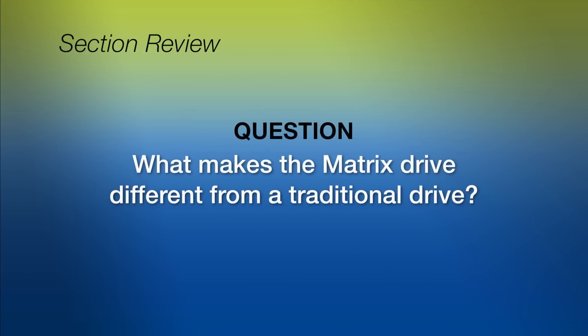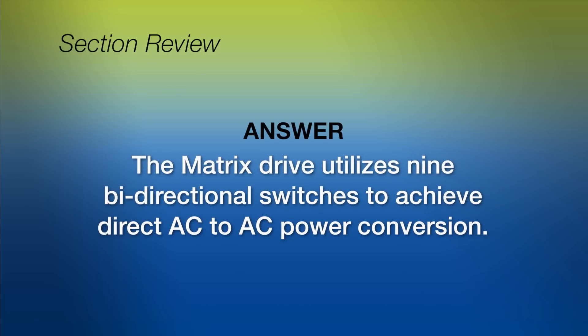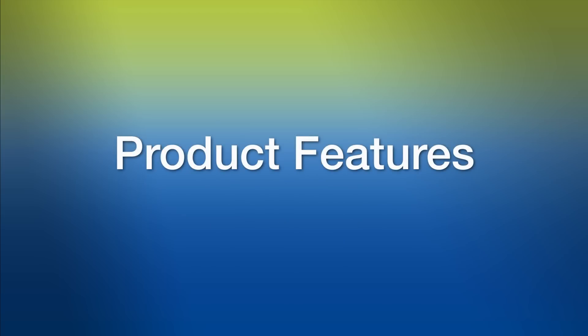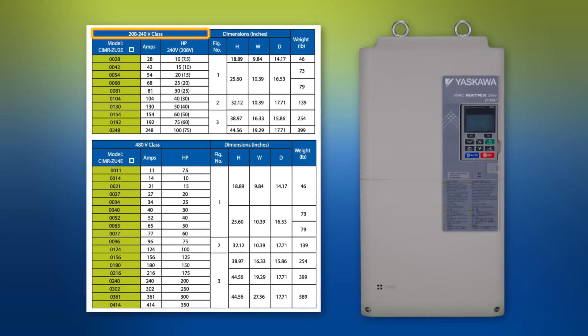What makes the matrix drive different from a traditional drive? The matrix drive utilizes nine bi-directional switches to achieve direct AC to AC power conversion. The U1000 is available for two voltage classes. In the 240 volt class power range, models are available from 28 amps up to 248 amps. In the 480 volt class power range, models are available from 11 amps up to 414 amps.